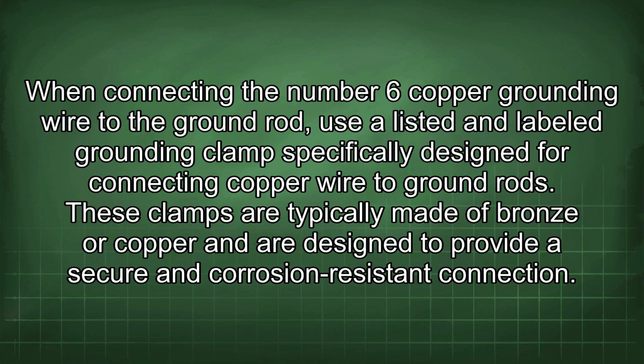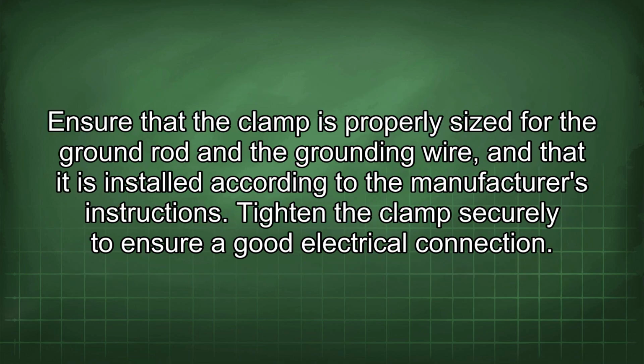When connecting the number 6 copper grounding wire to the ground rod, use a listed and labeled grounding clamp specifically designed for connecting copper wire to ground rods. These clamps are typically made of bronze or copper and are designed to provide a secure and corrosion-resistant connection. Ensure that the clamp is properly sized for the ground rod and the grounding wire, and that it is installed according to the manufacturer's instructions. Tighten the clamp securely to ensure a good electrical connection.